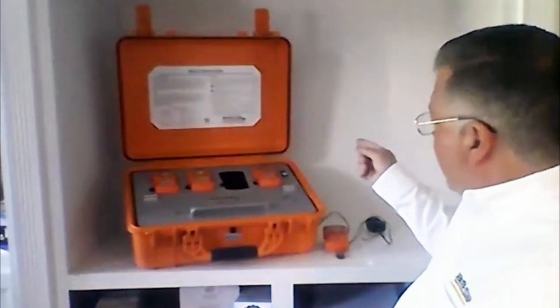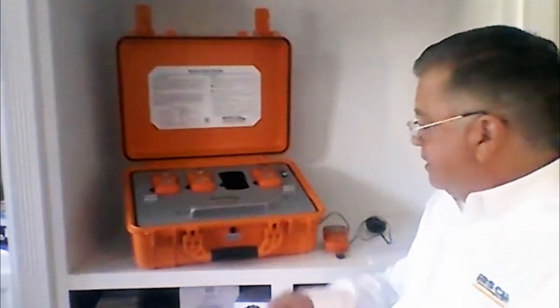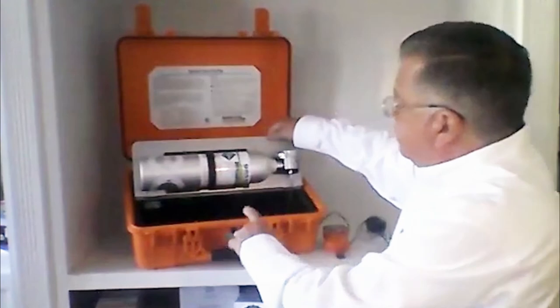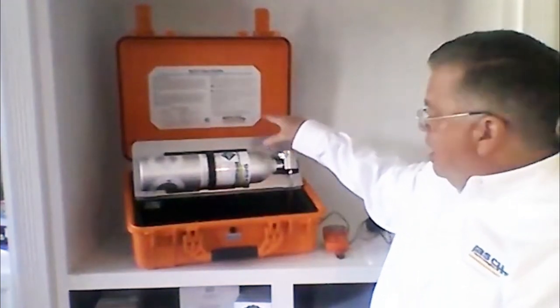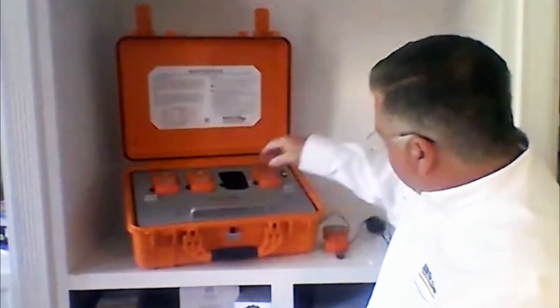Today I'm going to be showing you our GCT docking station. Our document stations are designed for bump testing and calibrating our gas detection units. They're built with simplicity and ease of use in mind, and they're very rugged and also very portable. As you will see here, we have four bays, which means that we can bump test or calibrate four units at a time. The quad gas is in the cylinder here, which is attached to the regulator and secured by the strap.